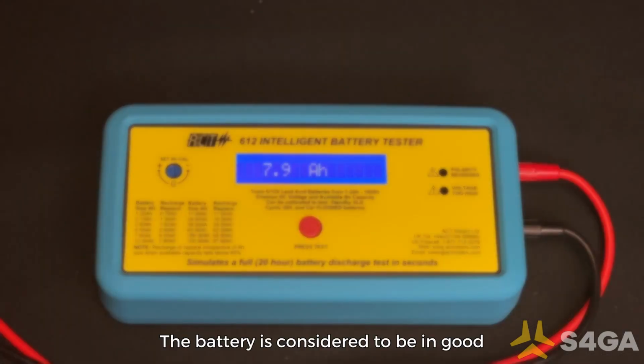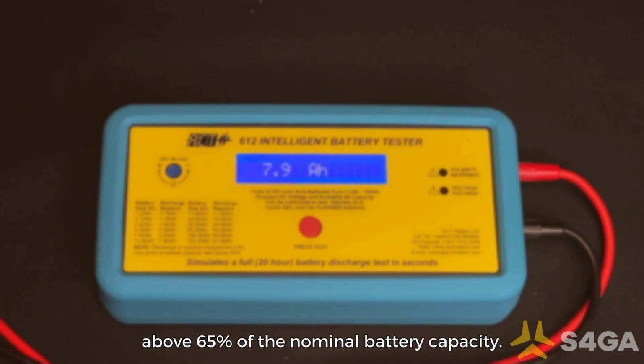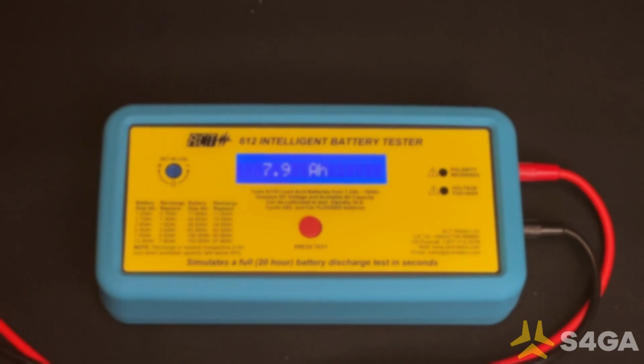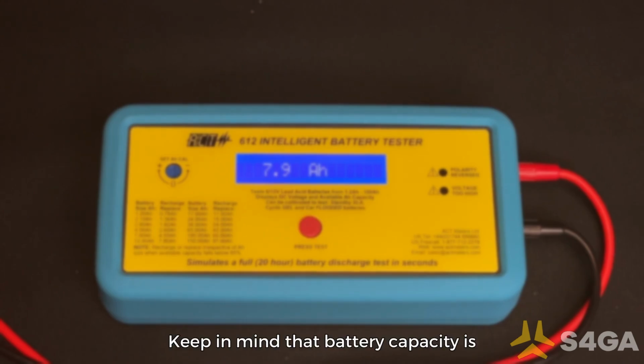The battery is considered to be in good condition when the measured capacity is above 65% of the nominal battery capacity. The battery is considered okay if a capacity above 5.85 Ah is measured. Keep in mind that battery capacity is temperature dependent, with optimal testing conditions between 20 degrees Celsius and 25 degrees Celsius. Repeat the same procedure to test the second battery in the lighting unit.